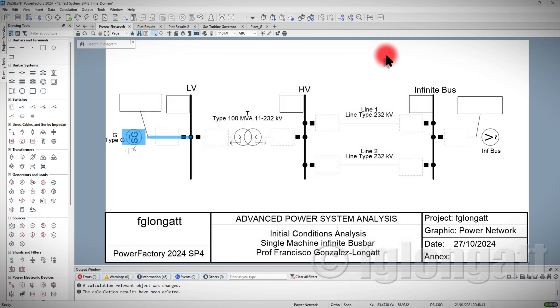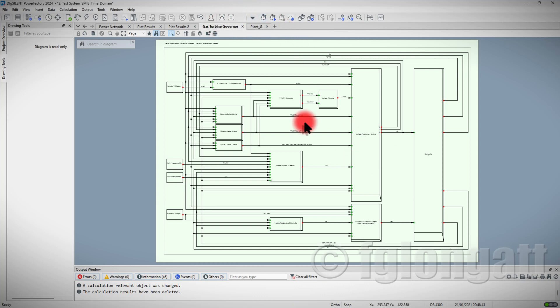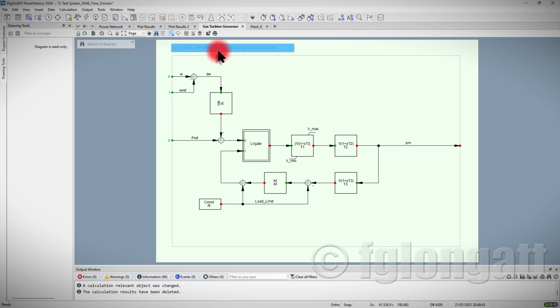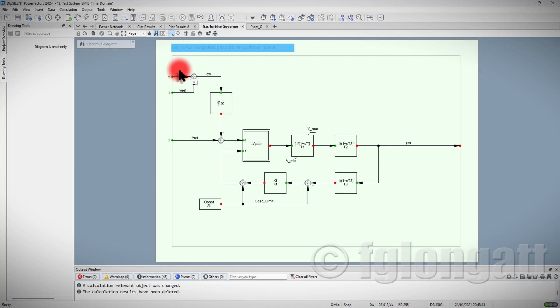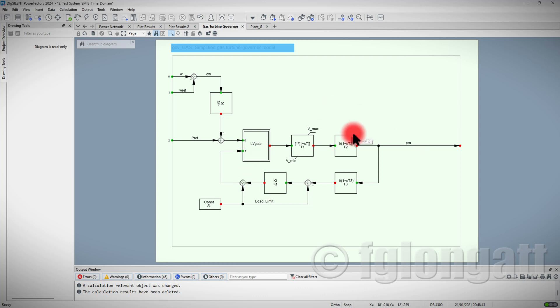What I want to tell you is that PowerFactory spent a lot of time creating this governor over here. You can see that this is a simplified gas turbine governor model. You can see over here the inputs, rotational speed and rotational reference. You can see over here the active power reference. You can see here the output, that is the mechanical power, and some blocks diagram representing what we know as the governor model.